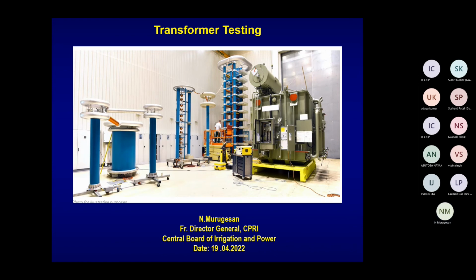Overload results in what? Overloading causes what effect on the transformer? Aging effect, heating - aging effect. So what happens is the heat will degrade the insulation properties of the material. That is why the transformer should be kept at normal temperature or whatever guaranteed temperature. As the temperature increases, the insulation is the major first casualty - the insulation properties will go down, deteriorate.